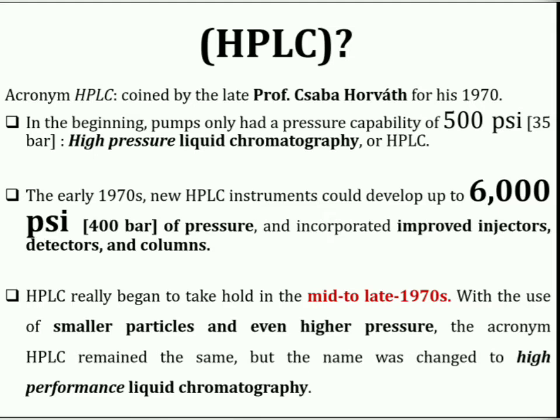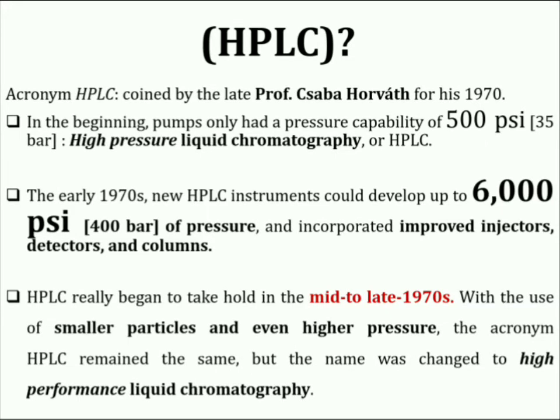The early 1970s saw a tremendous leap in technology. These new HPLC instruments could develop up to 6000 psi of pressure and incorporated improved injectors, detectors, and columns. HPLC really began to take hold in the mid to late 1970s with continued advances in performance. Smaller particles and even higher pressures were used, and the acronym HPLC remained the same but the name was changed to high performance liquid chromatography.